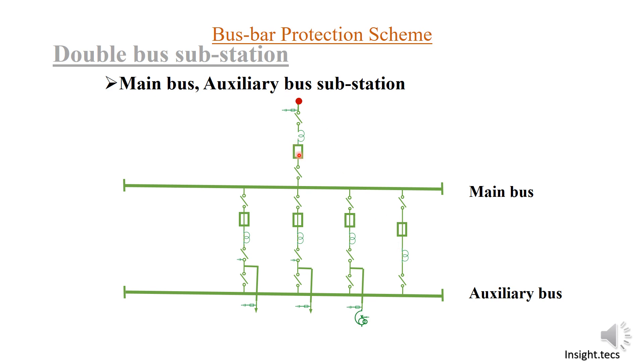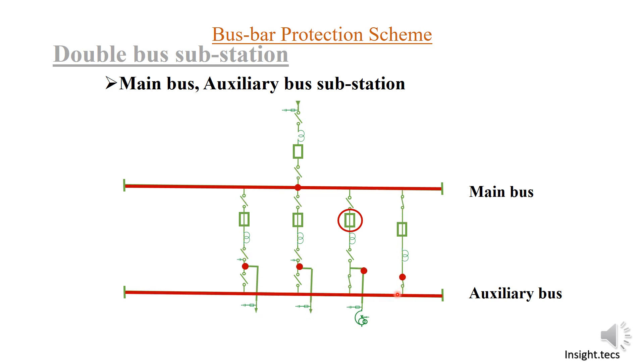Suppose power is flowing from this feeder — it will charge the main bus and through the outgoing feeders it will flow out. Now what happens if one of these breakers is not working? If there is an issue in one of these breakers and because of that you cannot charge this transformer, we will use the bus coupler and close the isolator of the auxiliary bus. Closing the bus coupler, power gets transferred to the auxiliary bus, and through the auxiliary bus isolator power will now flow into this transformer. This is how the auxiliary bus arrangement works.